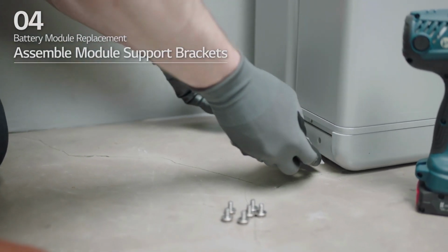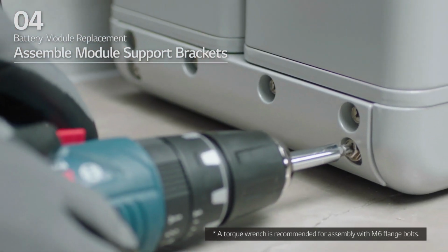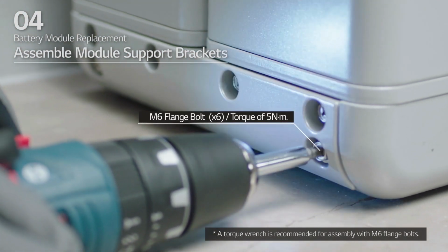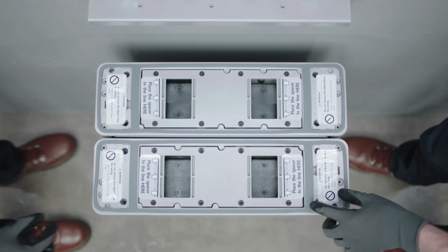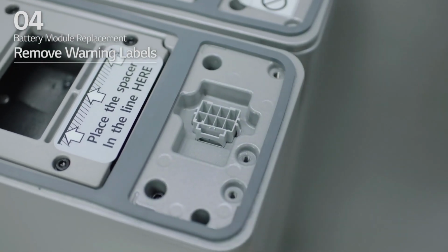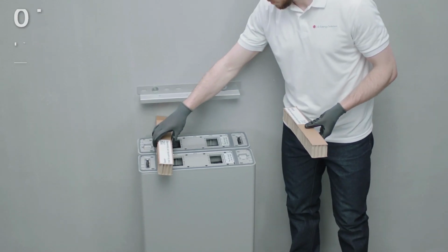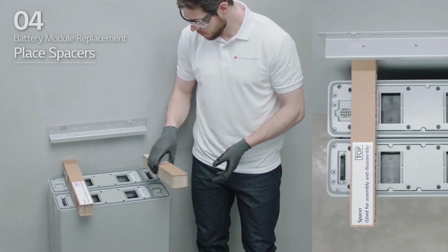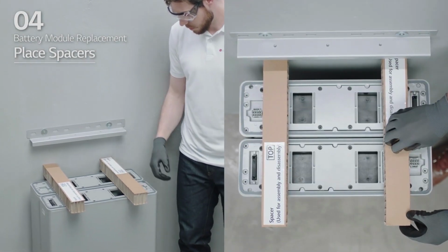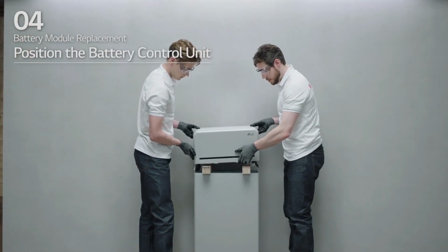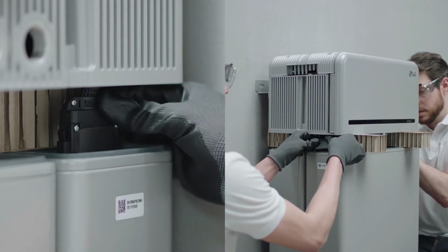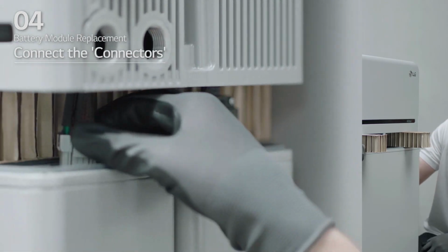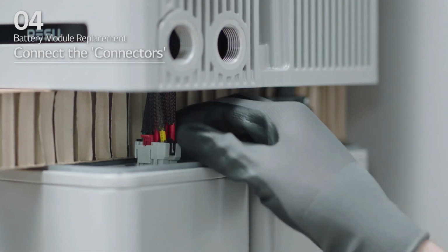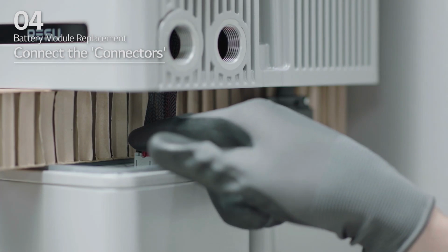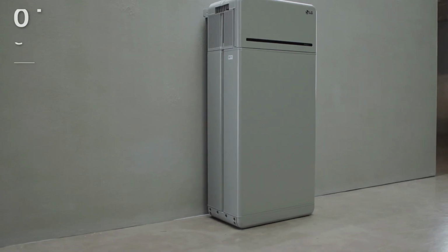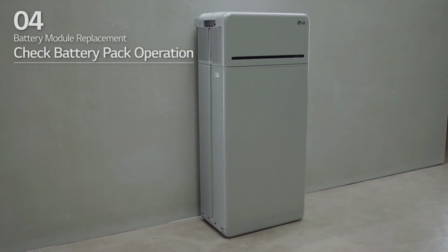Assemble the module support brackets and tighten them using 6 M6 flange bolts with a torque of 5 Newton-meters. Remove the warning labels from the battery modules. Place the spacers at the positions marked by the labels on the battery modules. Place the battery control unit on top of the spacers. Then, connect the 2 power connectors and 2 sensing connectors until you hear a click. After that, check that the battery pack is operating properly.